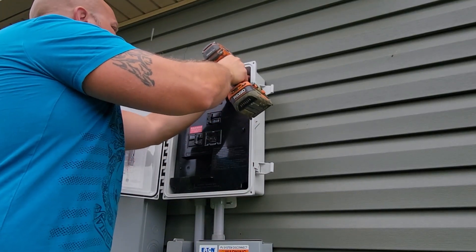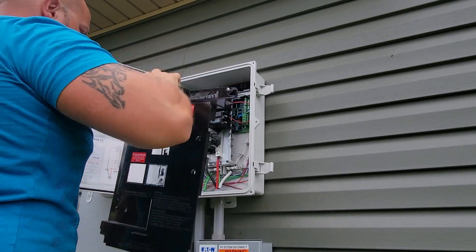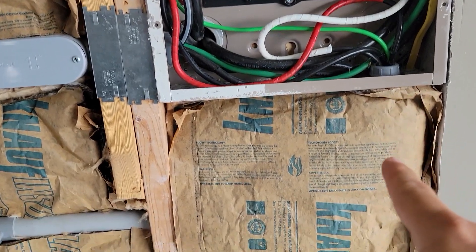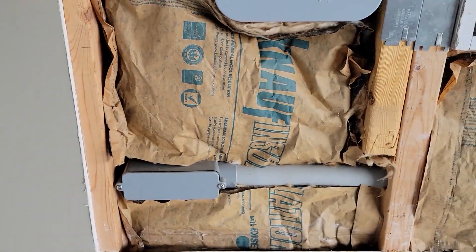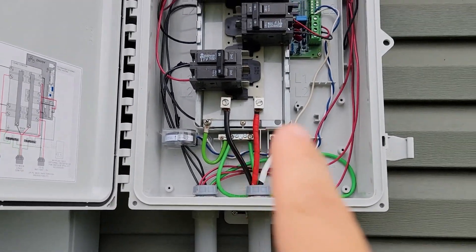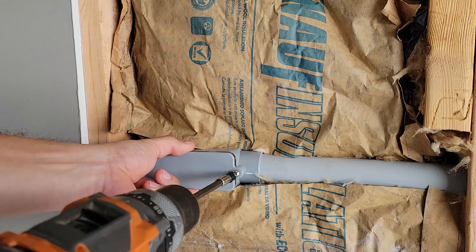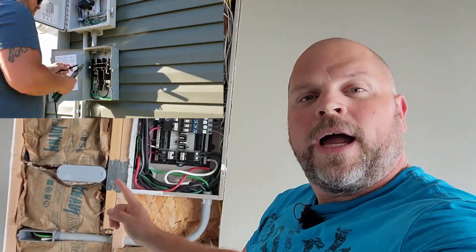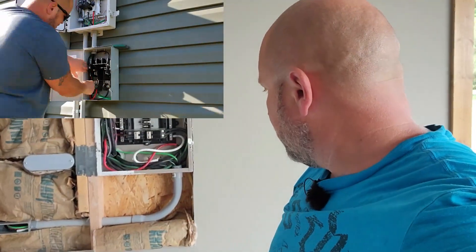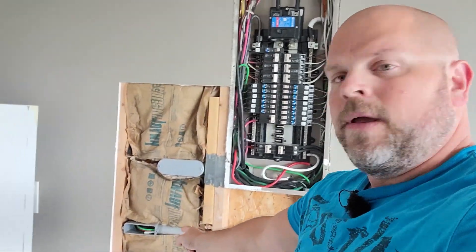We're going to start our wires coming in, coming down. This is an elbow, comes over, goes through into those boxes outside. And then once we come to the outside, it'll come through here, go up through that, up through here, over, and connect into the control panel. We'll route this down. And for you guys that have subscribed to the channel or have been following along in this entire solar project, you've seen my video on how I got this installed — I'll put a link right up here. But we are now ready to start fishing our wire through this pipe down and then out.